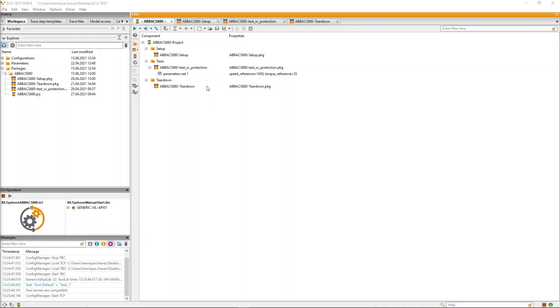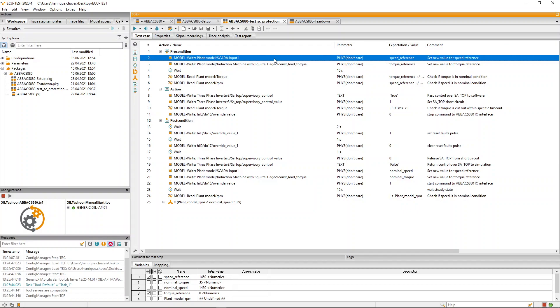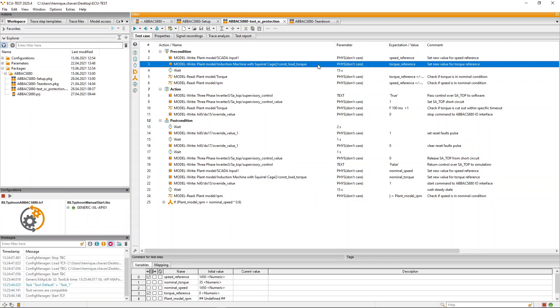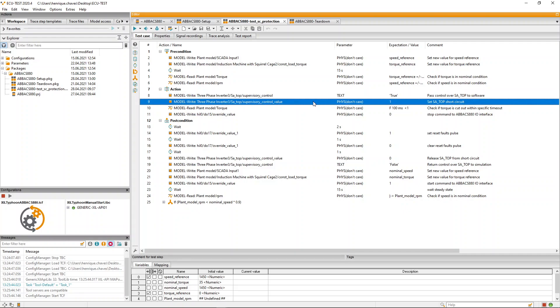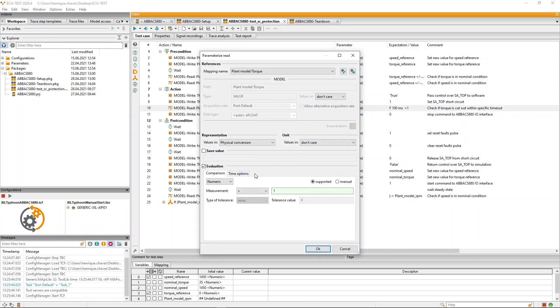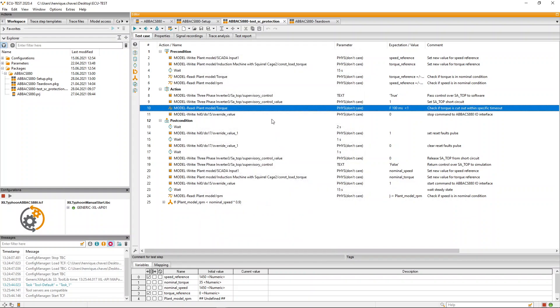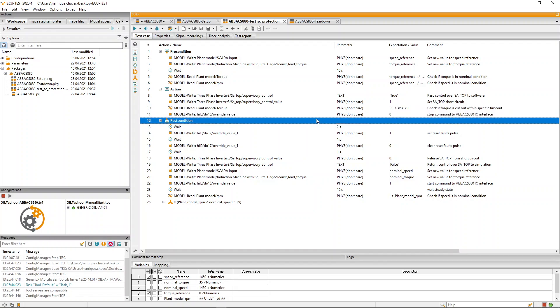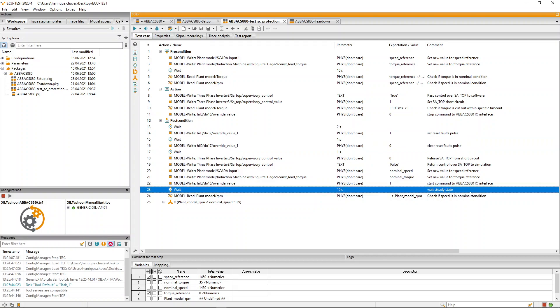Then we will have the test case package. In this test, we place the motor speed and torque to full load. Then we pass control of the IGBT switch SA_TOP to the software. By doing this, we can force an IGBT short circuit and bypass the PWM signal from the controller for this specific switch. When we force the switch to short circuit, we can read the torque and assert that the torque is cut off in the simulation within a 100 millisecond timeout. We then send a stop command to the controller to stop the drive. We use the post-action block to reset faults and re-establish steady state condition in the simulation to make sure the drive recovers from the fault.